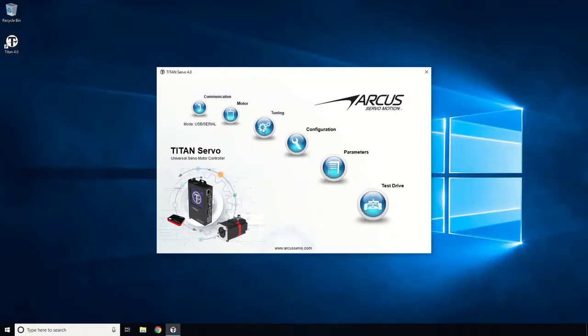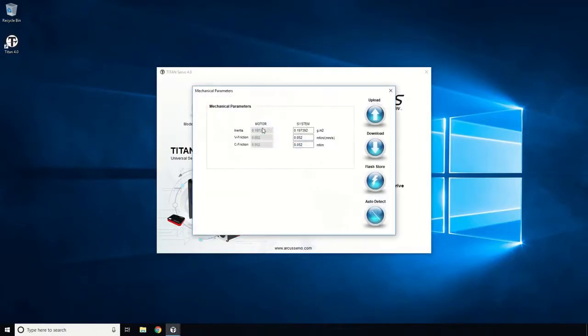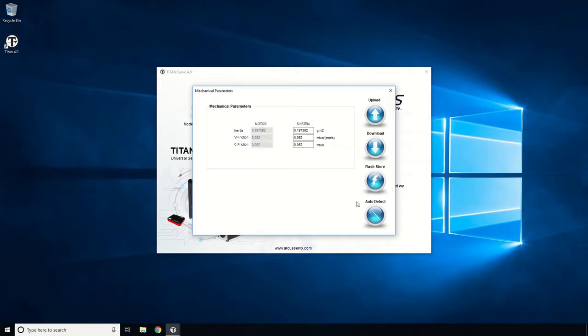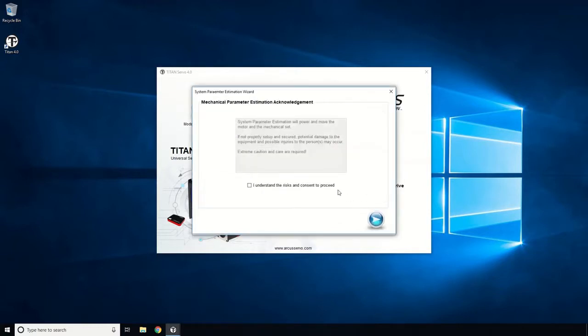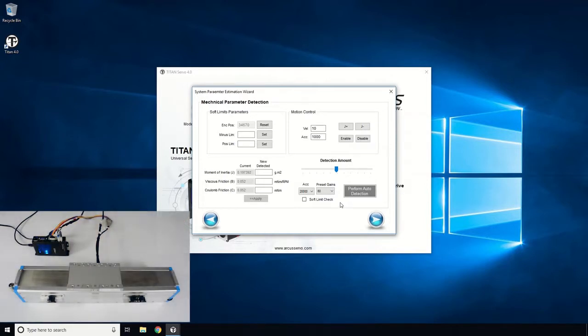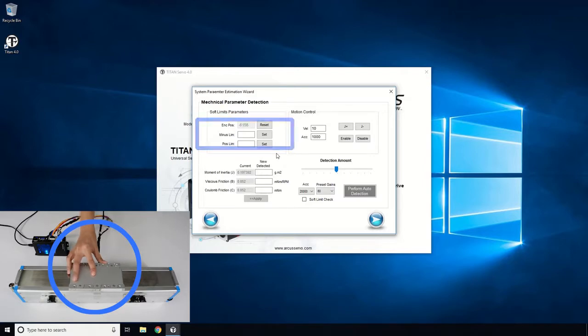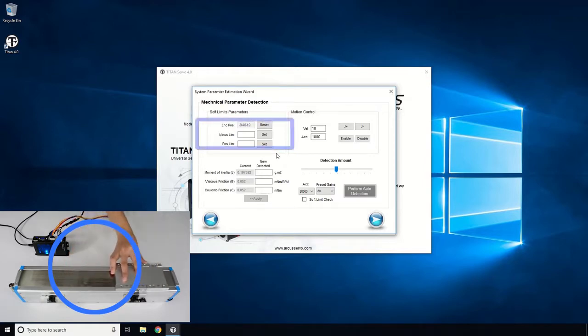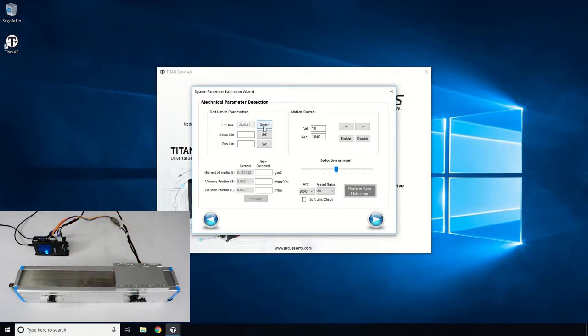Next, open up the tuning window. This process will detect the mechanical parameters, which are the inertia, coulomb, and viscous friction values. Click on the Auto Detect button and consent to proceed. First, we will need to set up the end of travel positions for safety. Manually move the stage to the negative end and reset the position as 0. Let's also set this as the minus soft limit.